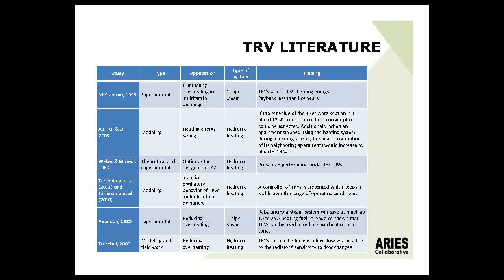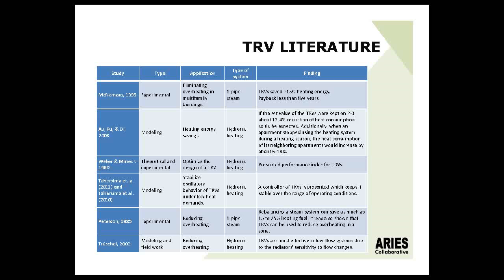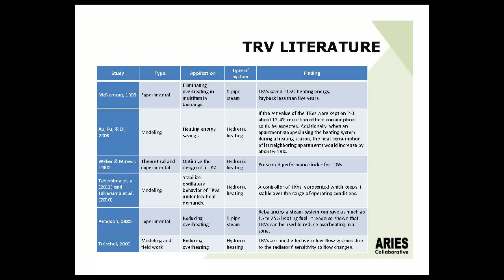The most notable was an extensive 1995 study sponsored by the New York State Energy Research and Development Authority, or NYSERDA, in which TRVs were installed in a number of buildings using one-pipe steam primarily, and most of those with standing radiators. That study determined that they were saving about 15% of energy after implementing those measures. Most of these other studies are either modeling or not specific to one-pipe steam implementation.